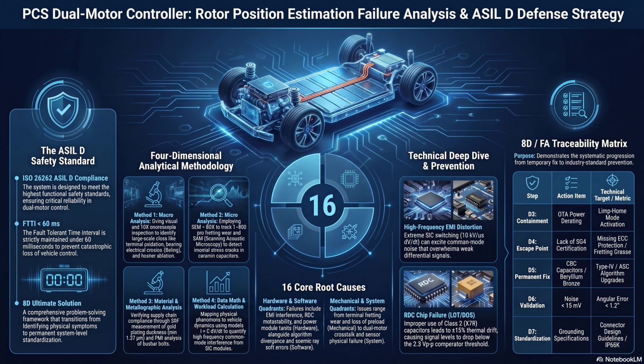That is wild. Okay, so the next physical saboteur involves those capacitors we were scanning with acoustic waves earlier: thermal drift. The documentation points out that substituting a stable capacitor with a cheap Class 2 X7R ceramic capacitor in the analog front end is a catastrophic error. Yeah, to understand why, you really have to look at the dielectric material. Class 2 X7R capacitors use a barium titanate crystalline structure. Okay, barium titanate. And barium titanate is ferroelectric, meaning its internal electric dipoles are highly sensitive to both applied voltage and extreme temperatures. So when the inverter compartment reaches, say, 125 degrees Celsius, the crystal lattice physically expands. And when it expands, the dielectric constant just plummets.